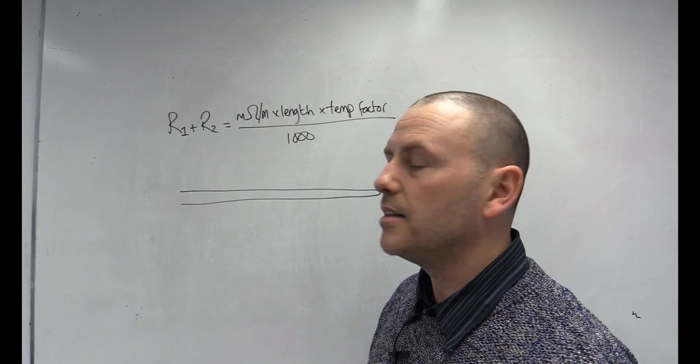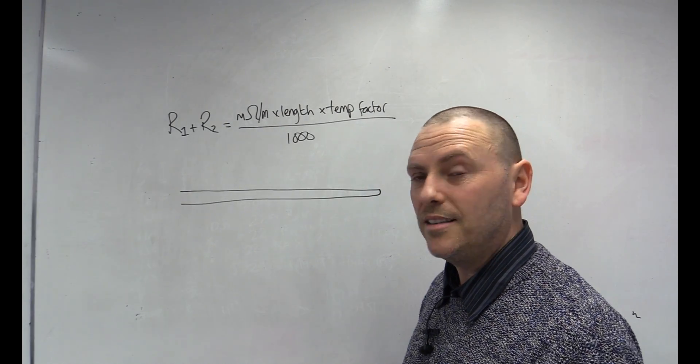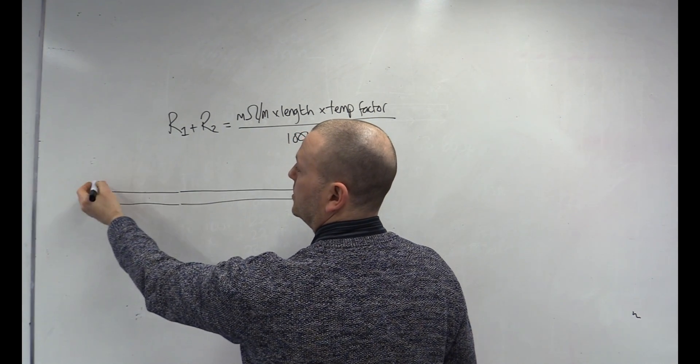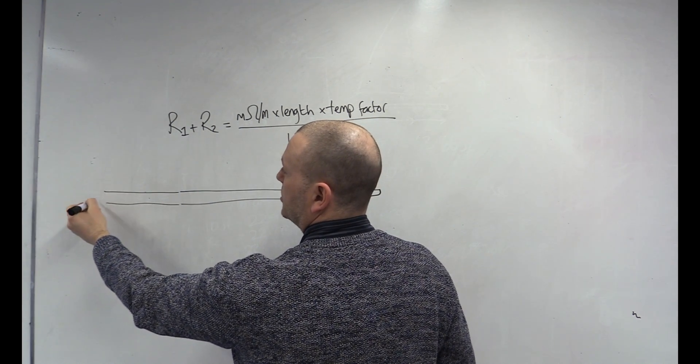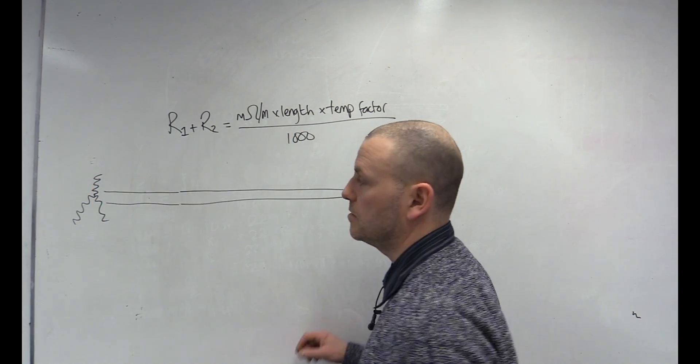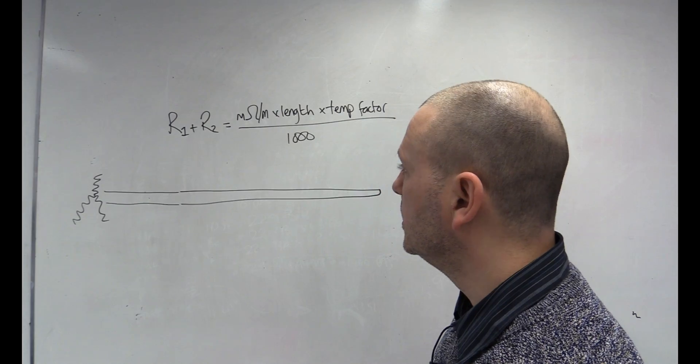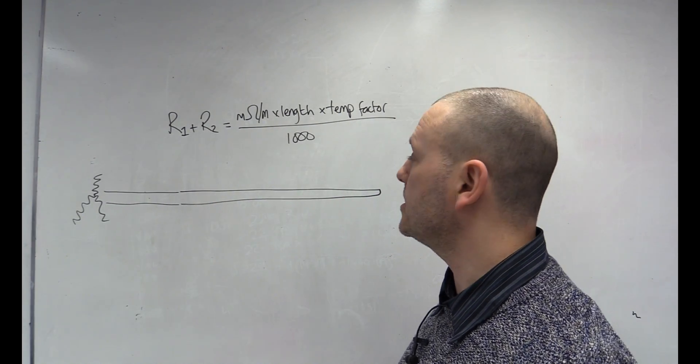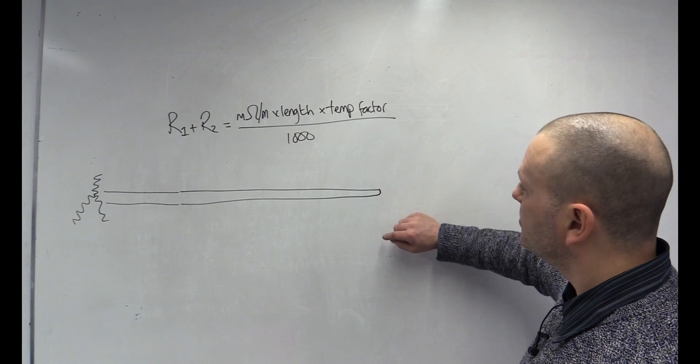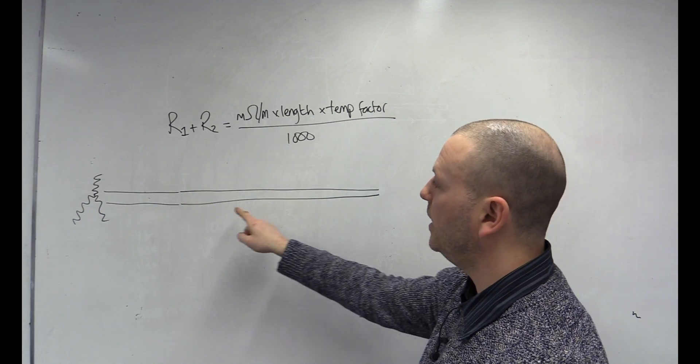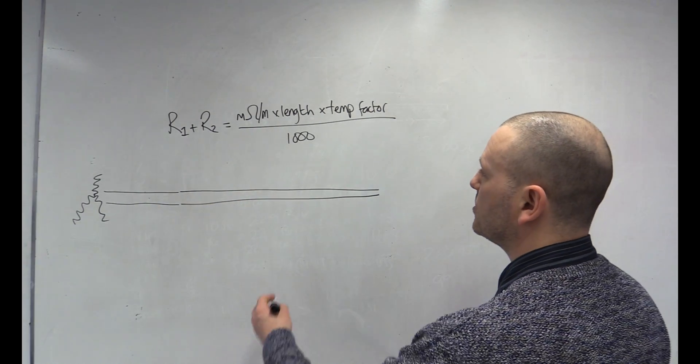Now, why do we need to know that? Well, because what we then do is add on the external part, which is the ZE, back to our substation. That's my drawing of a star winding. And then, once we've got that loop, we can understand how much current is going to flow if these cables touch here, or here.